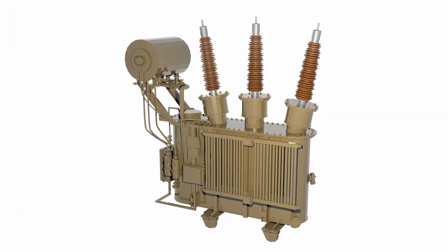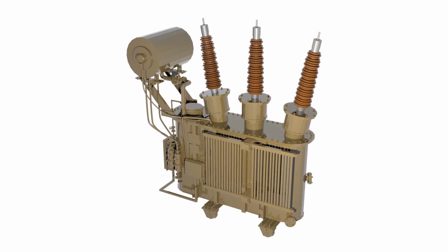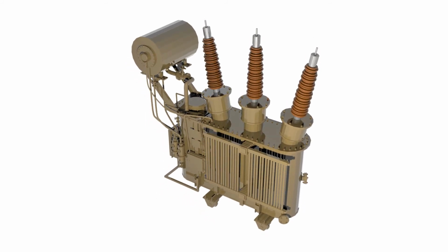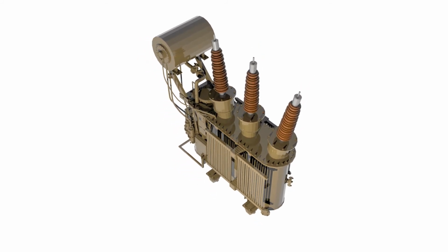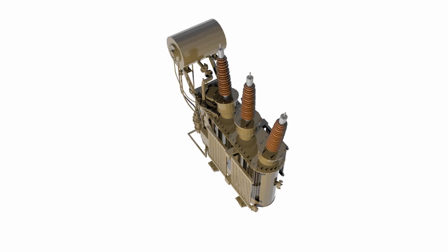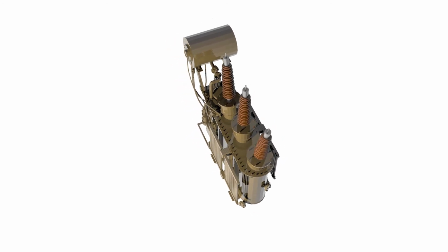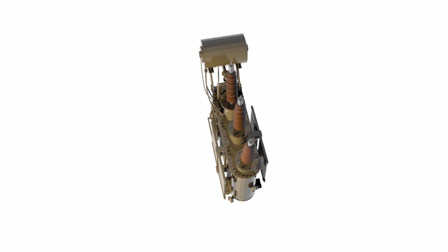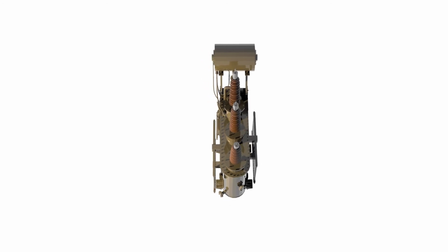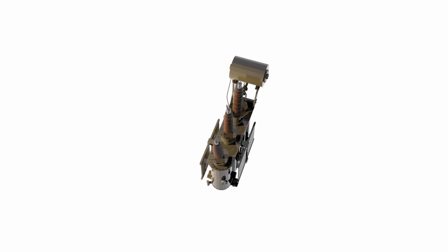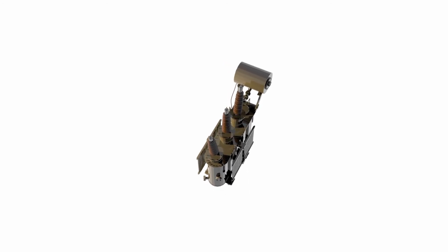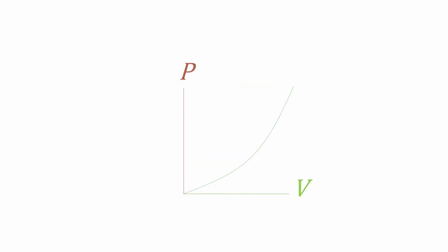the heat quickly. Both power losses mentioned before, hysteresis and eddy current, happen all the time the primary winding is connected to a power source. No matter if we have the secondary connected to a load, our transformer will be consuming energy. Of course this energy is not that high, but for a power transformer which can be connected every single day for a whole year, the total energy consumed is significant. For typical power transformers, the heat generated due to core losses can be compared to the heat generated by 10 heaters connected at the same time.